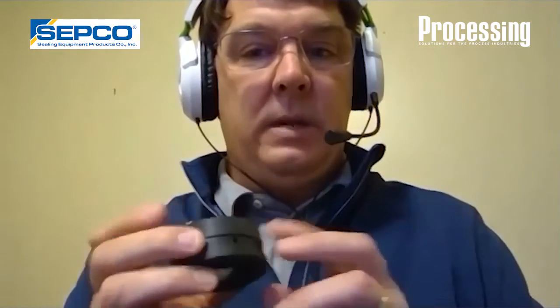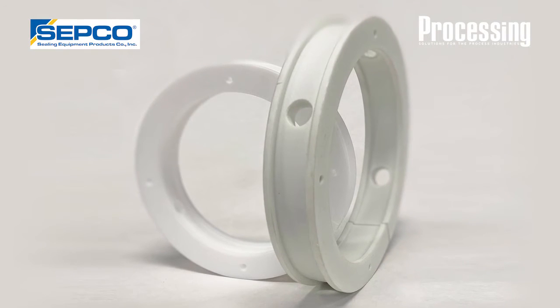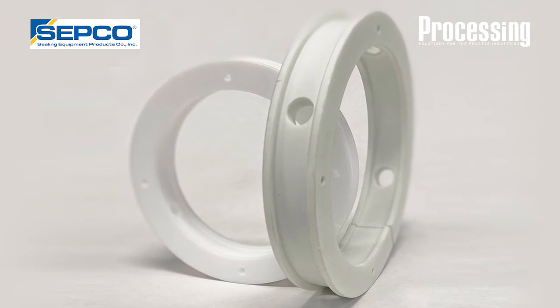But at its core, the air seal is the same as if it were to go into an auger or an agitator or a mixer. The only difference is that this seal always comes split. It will always be a split seal, and it actually will bolt up against the stuffing box. And then along with this air seal, Jesse, we will put a series of bushings. These are close tolerance bushings. SEPCO, we call them hydroloads. And we put a series of these along with a lantern ring as well inside the stuffing box.